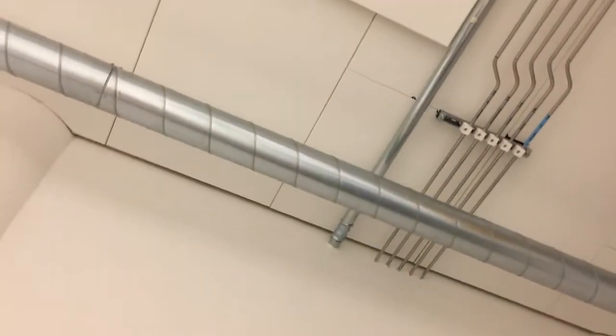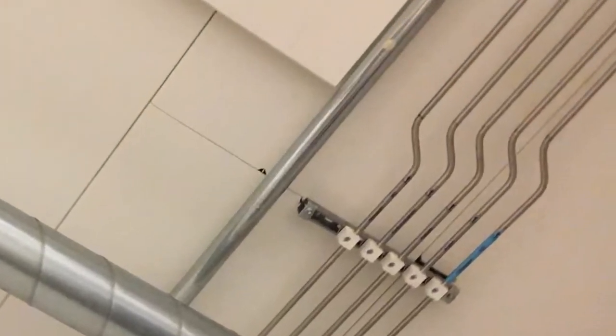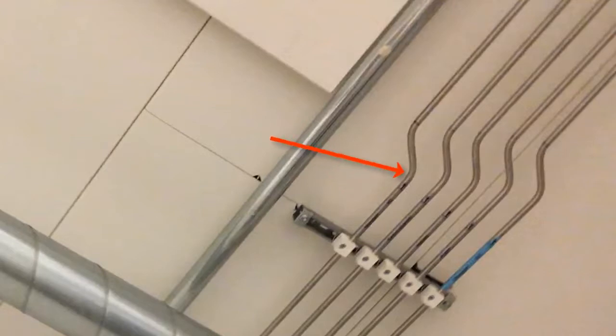These are some interesting pipes. Again you can see the length of some of these piping runs. Here's where they come into the room. They've come from ultimately probably a K-cylinder or bottle filled with each of five different gases we'll see in a moment. And here we have more of a drawn tubing, and so you can see the way this pipe is done. It's a stainless steel pipe and we have this drawn tubing and it's simply been bent in order to follow the profile that we want. So here we have an elbow that perhaps doesn't have the standard radius of some of the others, and we might have to think about that when we're trying to calculate pressure losses and such a thing. But there's a 45 degree bend and another 45 degree bend so that we can get these pipes going where we want them to go.